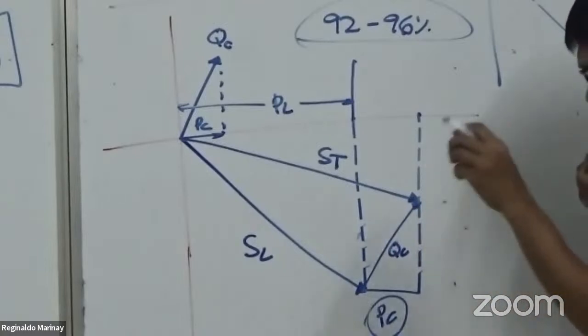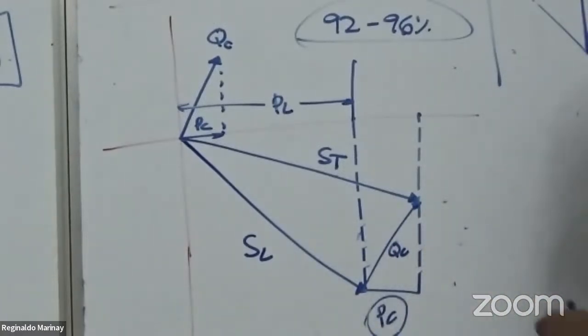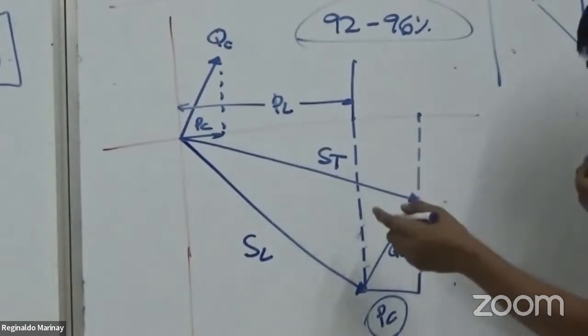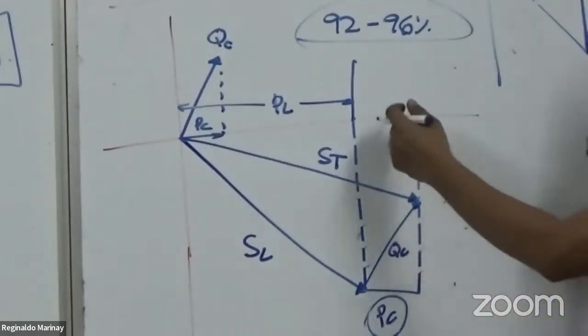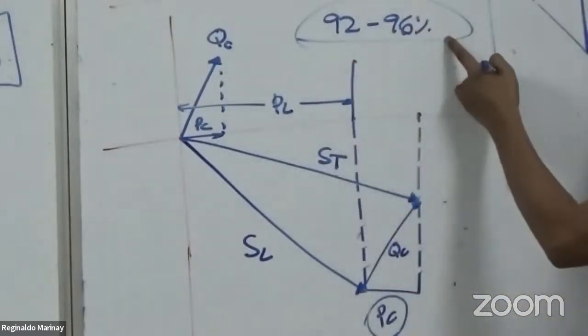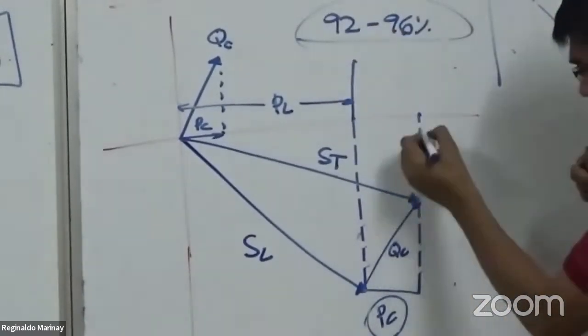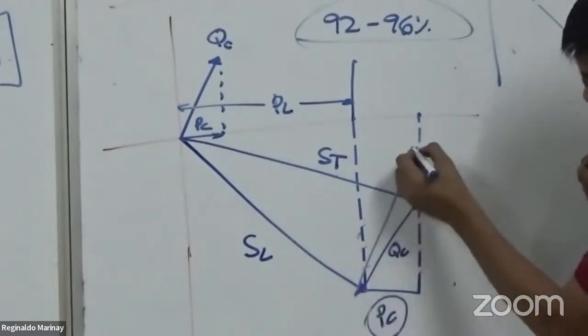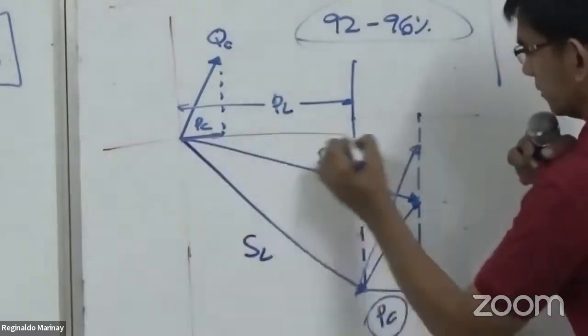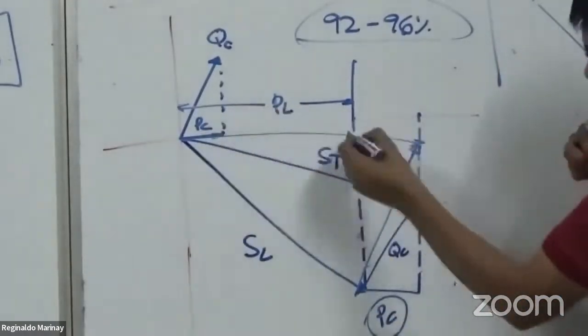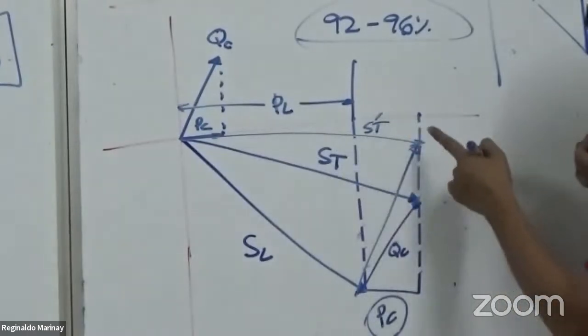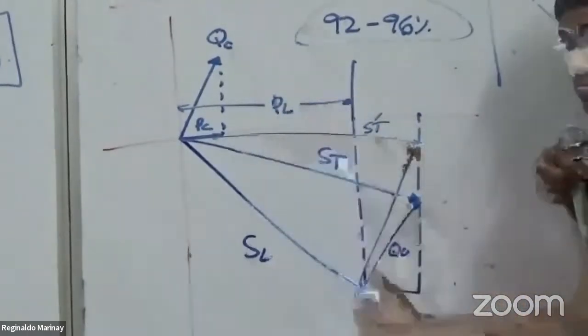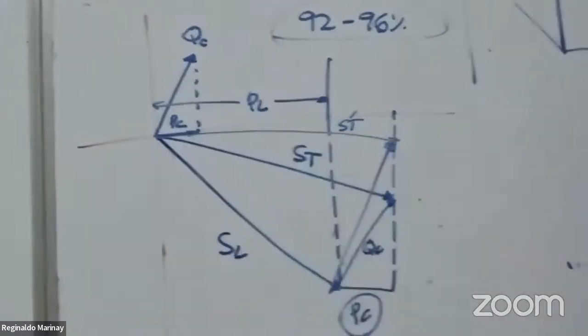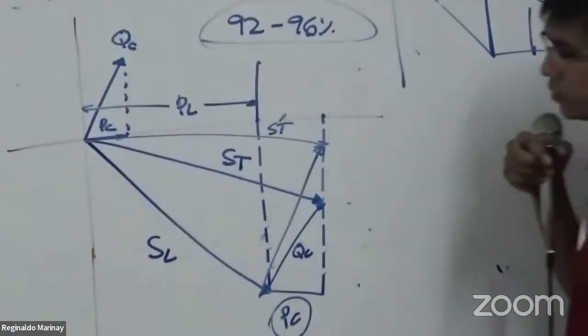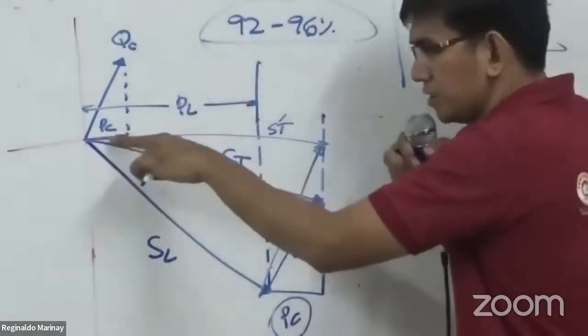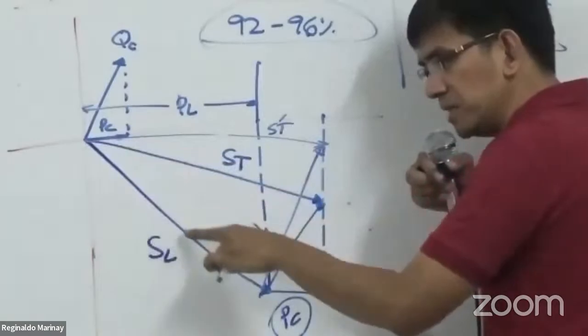So you better check your system. If you increase the value, see to it that it's less than 1, around 0.92 to 0.96, let's say somewhere here. And then from this point up to this point, if you find that this ST, the new ST prime, is lower than this SL, that's a good compensation, that's a good correction. The kVA here must be less than your original kVA.